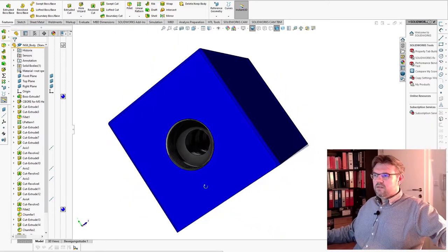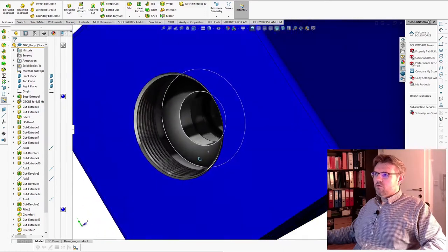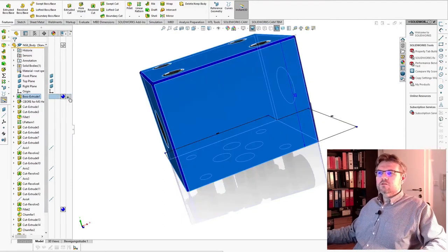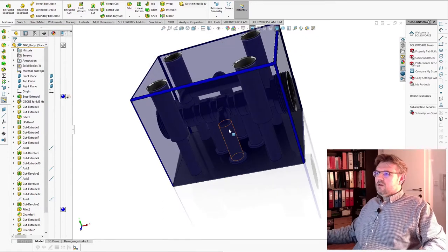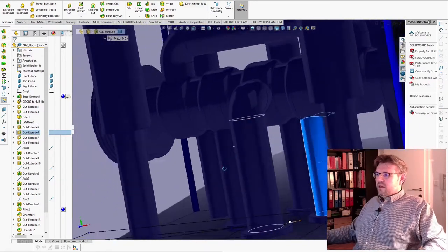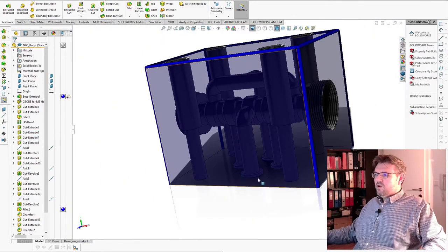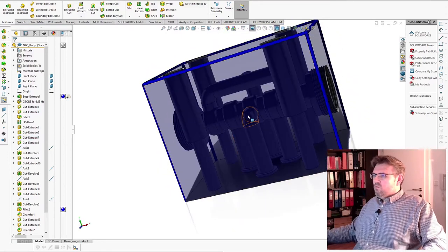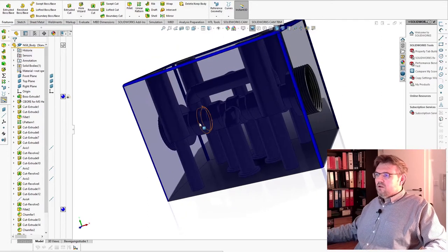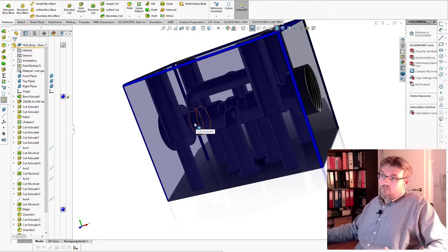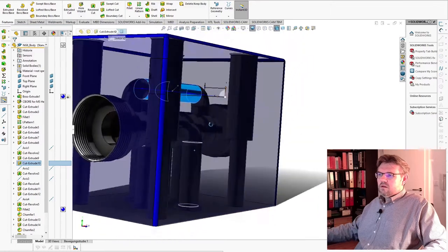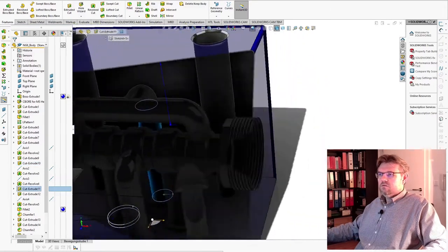Inside there is still a hole, now also with some chambers. Now let's have a look inside at how those connections are really connected to those chambers. You see, they are now slightly more complicated holes. Left and right, they are still directly connected. And this here is the pressure line. The pressure line is now connected with a hole going to the middle chamber. On the outside, left and right, there are two additional chambers, the fourth and the fifth one. Those two chambers are connected to each other and then connected to the other hole. This is the tank line.